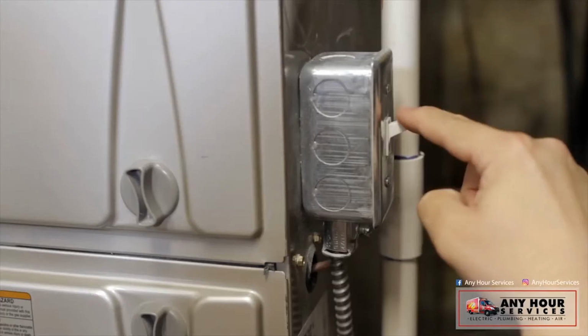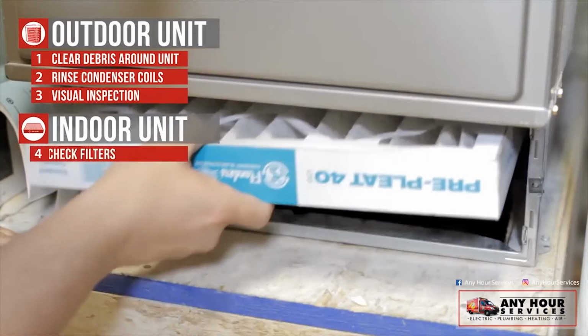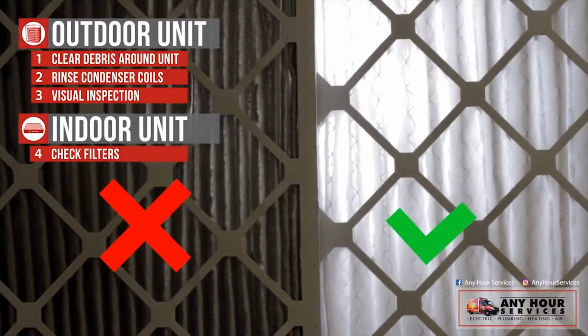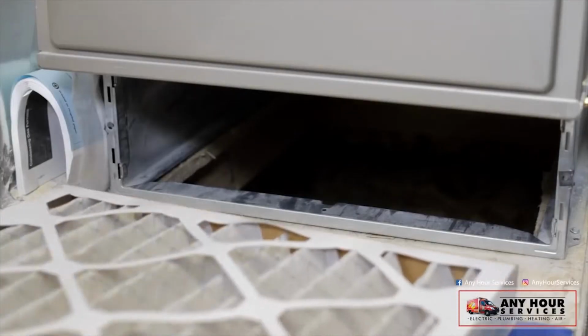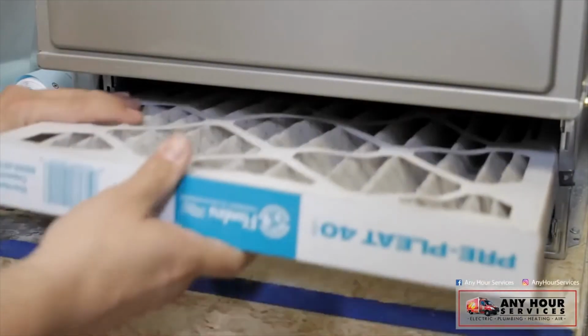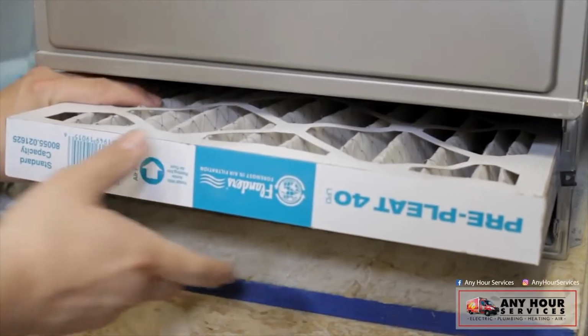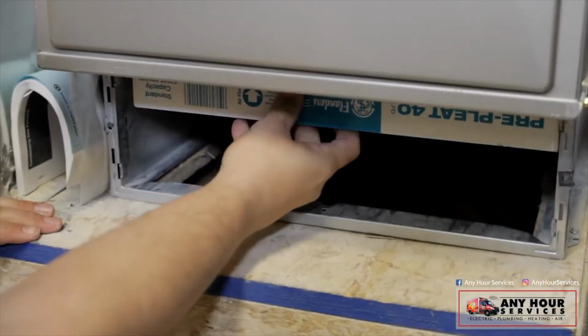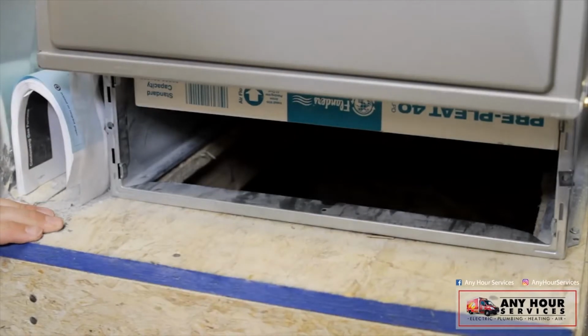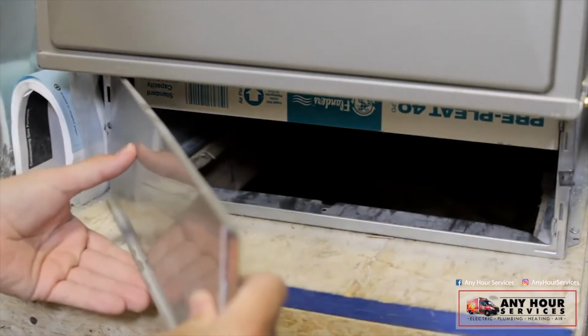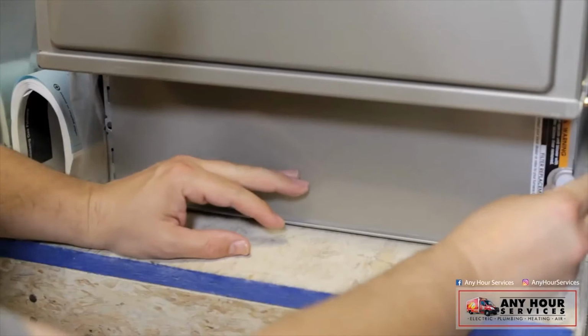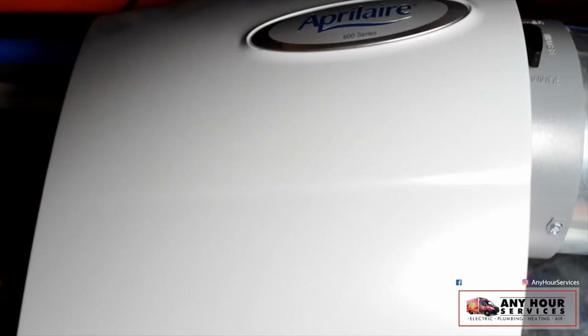Now let's go to the indoor unit, where your filters are. Start by cutting the power. Check the filters to make sure you can still see light through it. When replacing the filter, be sure to pay attention to the direction that the air is flowing. Make sure that the arrow on the filter lines up with the direction that the air flows through your unit. Replace filters as often as needed. This can be different for each home, so be sure to check it at least once a month.